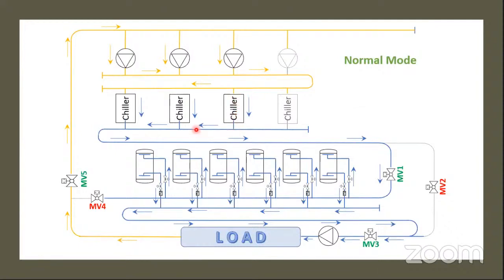when the chill water is coming out of the chiller, it is going inside the thermal storage tank first from the top, and these tanks are already charged. The chill water is not directly coming to the load. It is going first inside the tank, then coming out of the tank, and then being sucked by the secondary pump and being sent to the load. So here we see that a continuous replenishment of the tank water is happening, and this is the inline system.